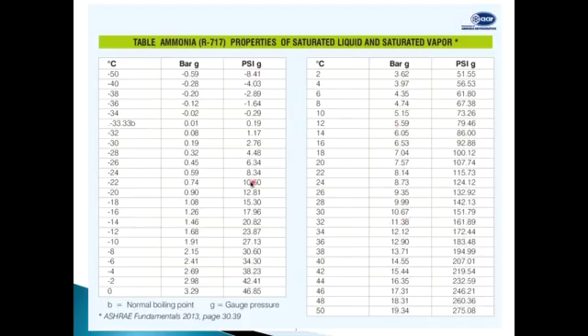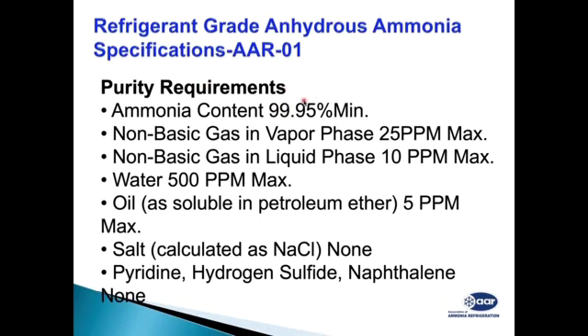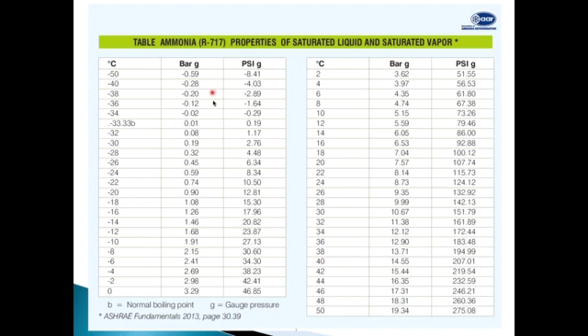as we all know, this is a typical refrigeration chart for saturated liquid and vapor. All our ammonia refrigeration systems depend on this chart. When we see that our plant is operating at, say, minus 40 degrees centigrade, a pressure of minus 0.28 bar by gauge pressure is there. It is best to assume that we have pure ammonia. Like this, 99.94% pure ammonia will give you minus 40 at minus 0.28 bar.